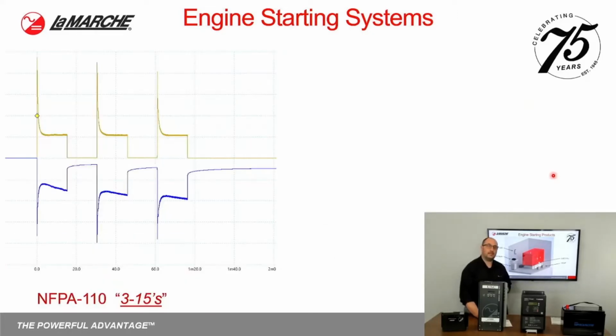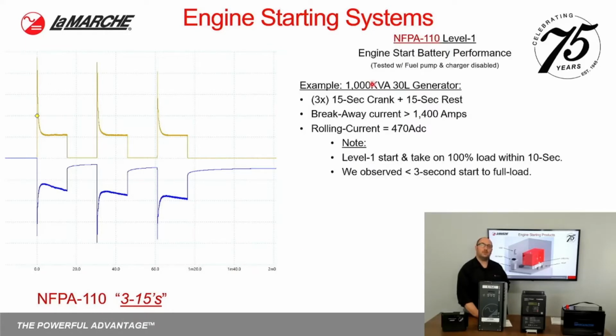So looking at this, we're going to talk a little bit about the current draw as well as the voltage fluctuation on the DC bus relative to engine starting. You're going to hear us talk about this term from NFPA 110 called 3-15's. So in NFPA 110, and looking at a level 1 system, and taking an example system of, like 1,000 kVA, that'd be approximately a 30-liter generator.